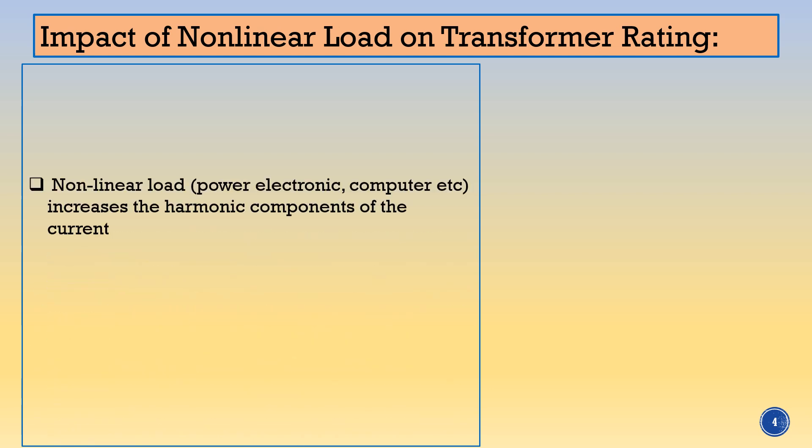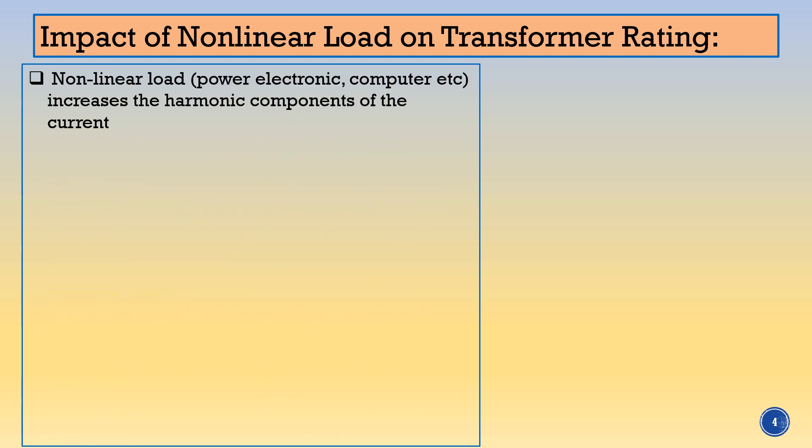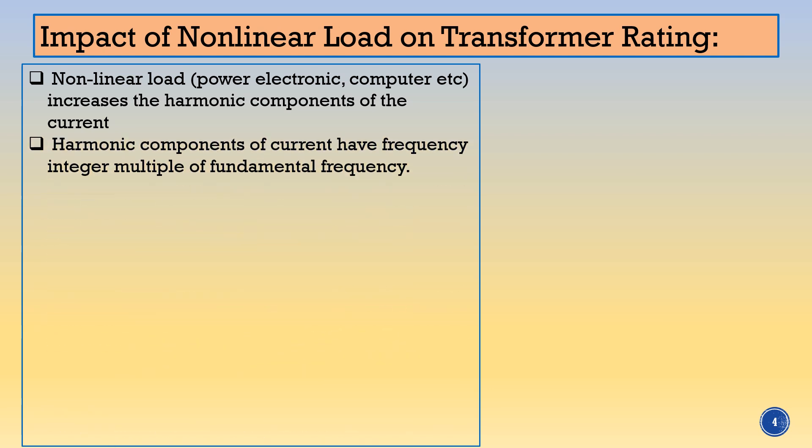In today's era, we know that electronic load and computer-related load keeps increasing. So due to the increase in nonlinear load, the harmonic component of the current also increases. The fundamental current in India is 50 Hz. But due to the use of electronic, computer, and switching equipment, the third harmonic at 150 Hz and fifth harmonic at 250 Hz signals are generated. The harmonic component of the current is the high-frequency integer multiple of the fundamental current.